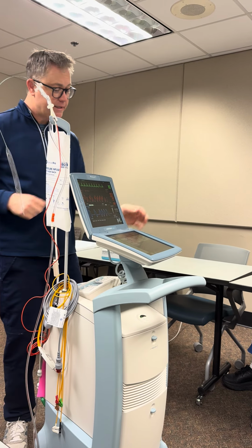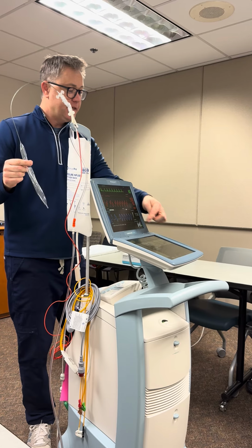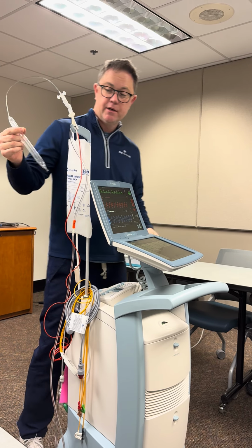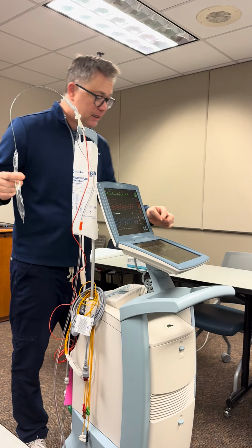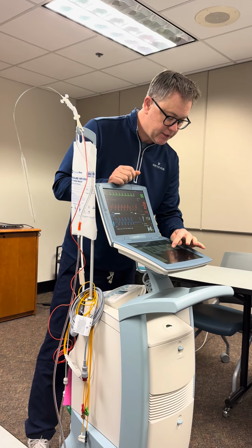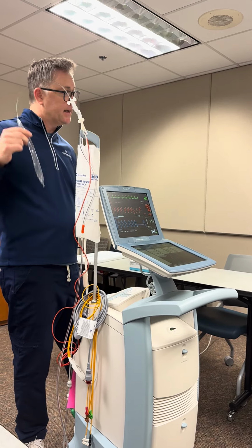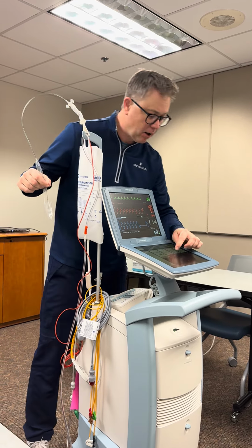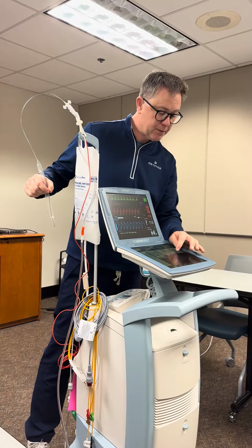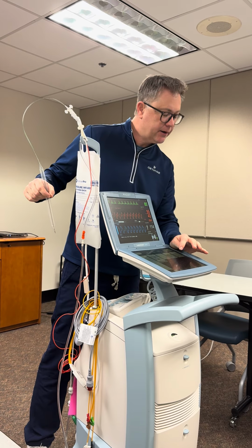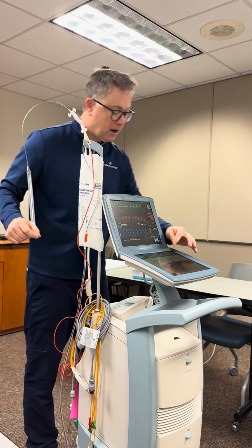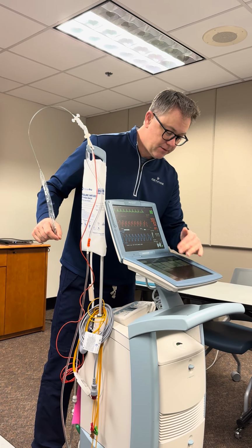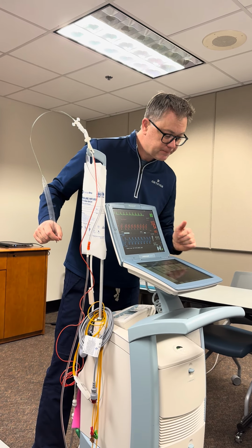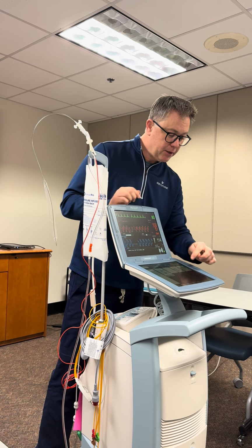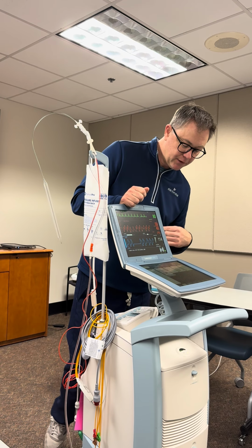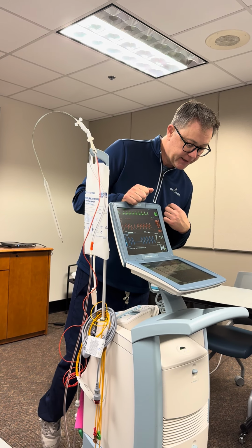Augmentation is another way to wean. At max augmentation, this balloon is always inflating at 100%. But another way to wean the patient would be to inflate this at like 90 or 80%. There are 10 bars here, and each bar represents 10%. You could knock this down to 90, 80, or 70%. That's what that augmentation is all about. And in the auto mode you do have the ability to tinker a little bit with the deflation timing if you wanted to, and that's where you would manage those.